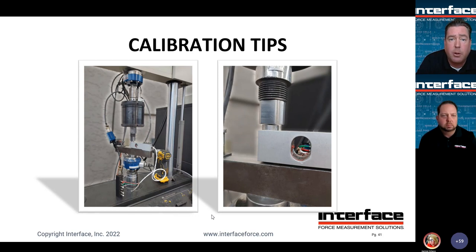A couple examples here. Well, actually, this is a single example, a couple different pictures. This is one of our model SSB load cells loaded into the calibration rig. You can see we've got a couple different load cells in the load string. One of these is the control load cell that provides force feedback to the frame control, and the other one is the reference standard. I believe the reference standard in this case is the load cell on the bottom, and the control load cell is on the top. That big spherical can in the center in this particular rig is our slack adapter assembly, slightly different than our standard configuration, but that's what we use on this particular frame.